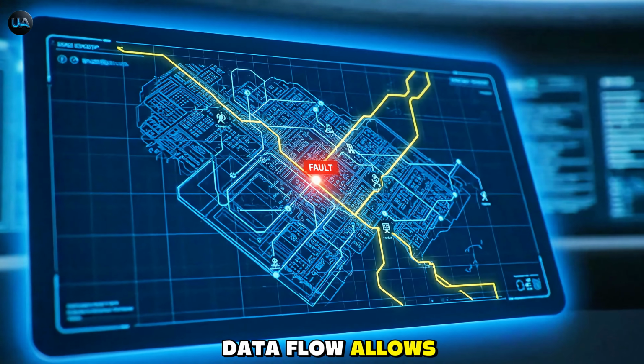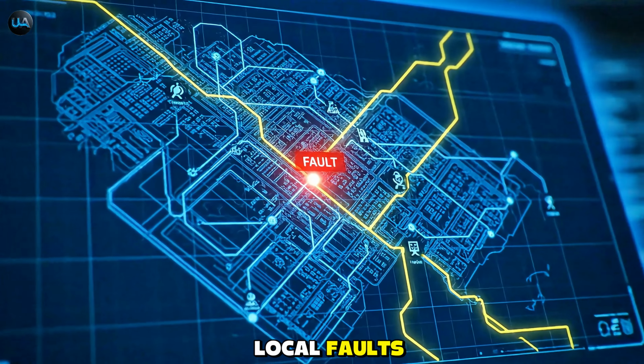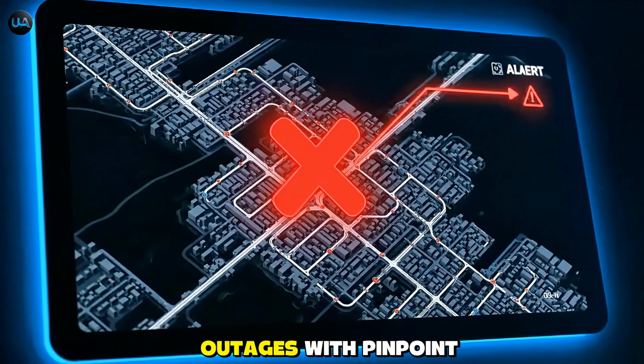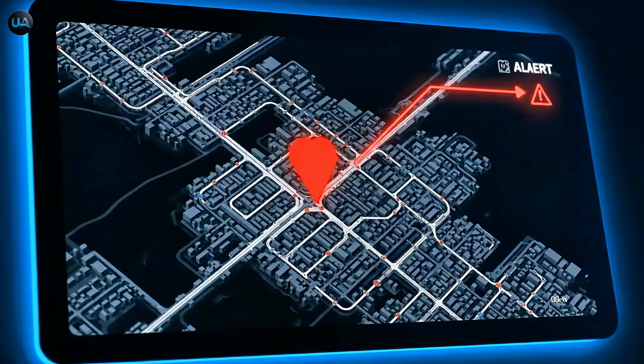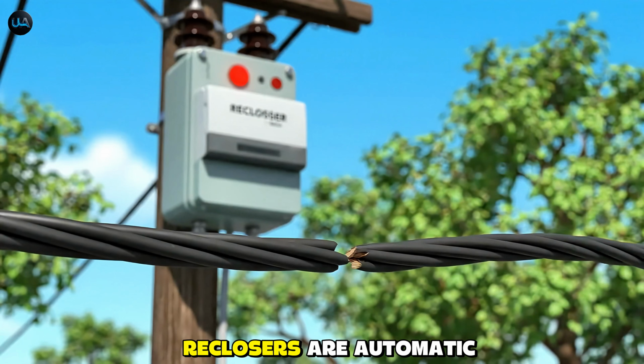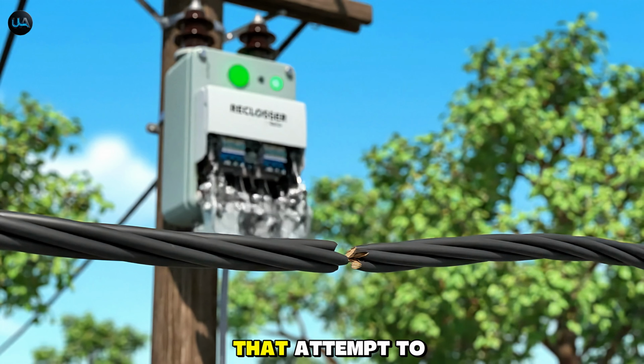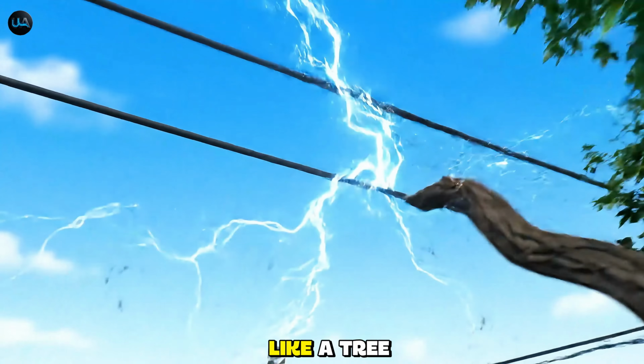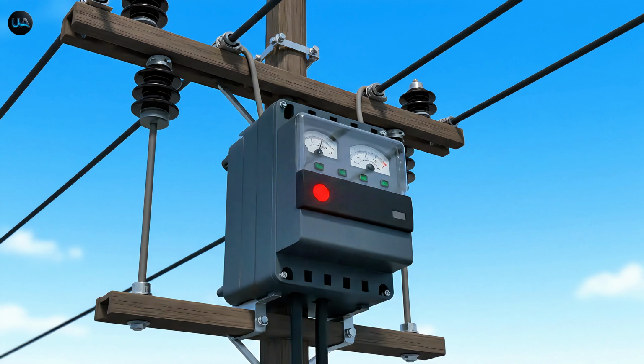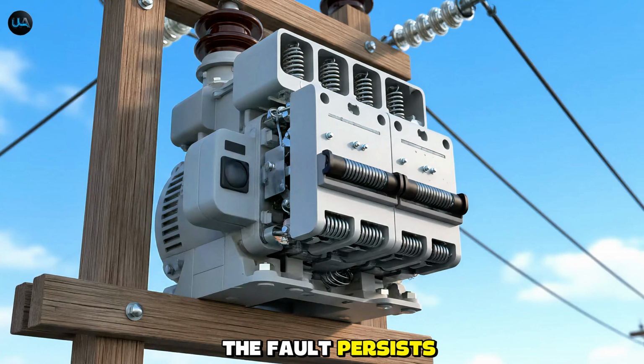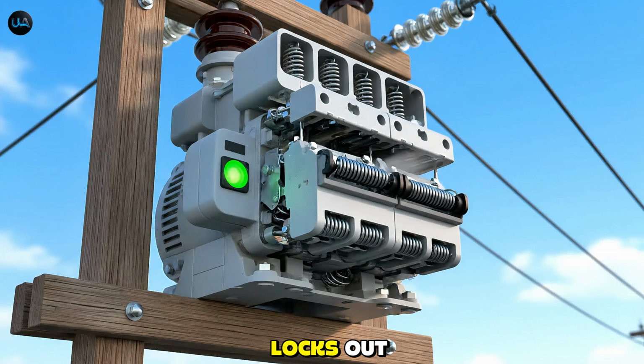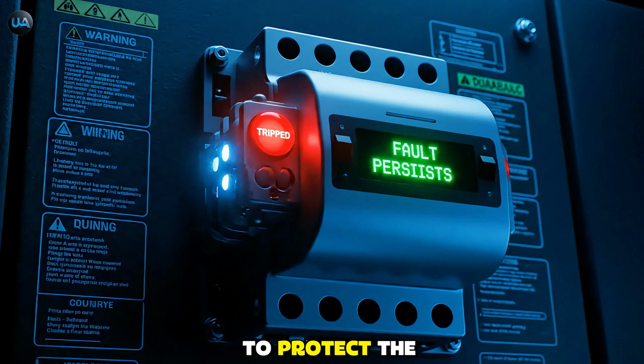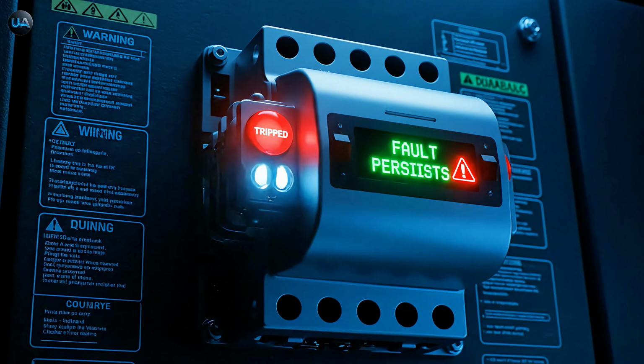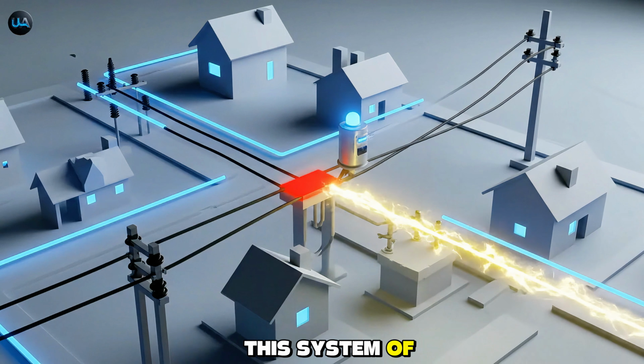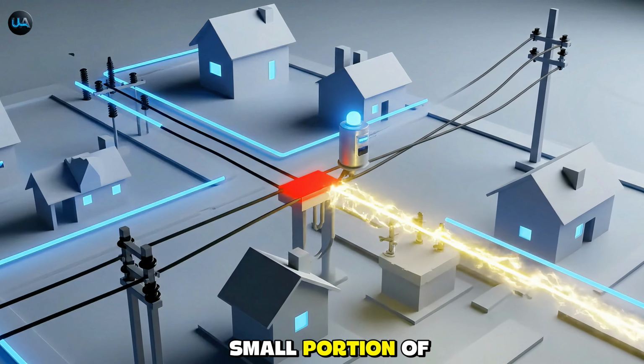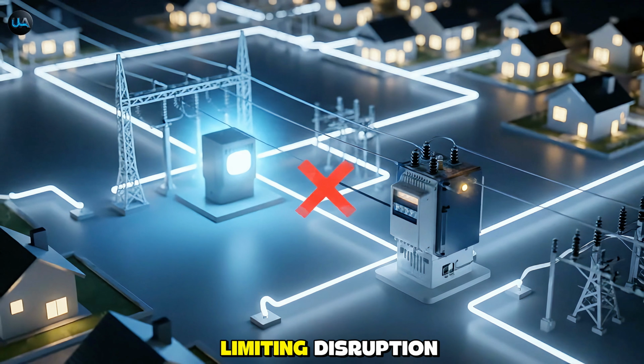This two-way data flow allows the utility to instantly detect local faults, balance neighborhood load, and respond to outages with pinpoint accuracy. Reclosers are automatic circuit breakers on the distribution lines that attempt to restore power after a temporary fault, like a tree branch hitting a line. If the fault persists, the recloser locks out, permanently isolating the section to protect the grid from continuous damage. This system of segmented protection ensures that only a small portion of the grid is affected by local faults, limiting disruption.